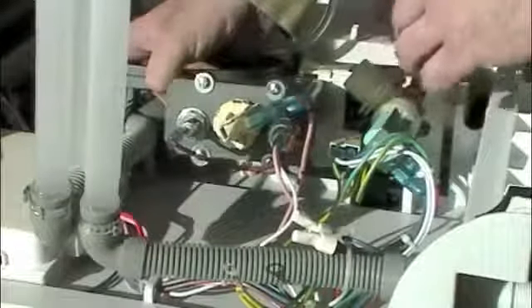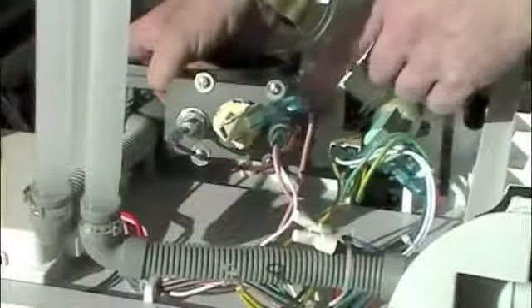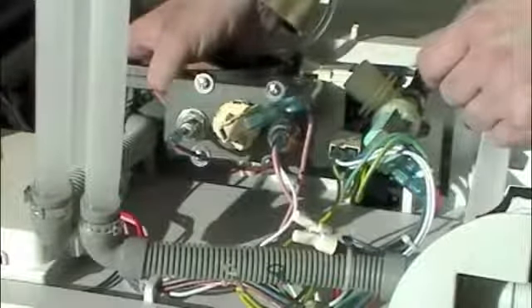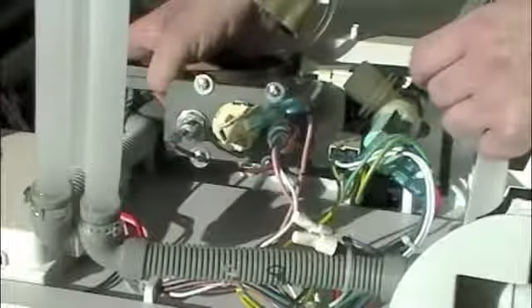To remove this element from its casing, you'll find two screws at the bottom, just like these two here at the top. We're going to pull all four of those, slide the element out of its casing, and then put the element back here in this lid, and then we'll go ahead and close it back up. And of course you're going to want to mark all your wires, make sure that you don't mix them up and you get those put back in the proper order. That will usually solve any heating issues that we're experiencing with the unit.